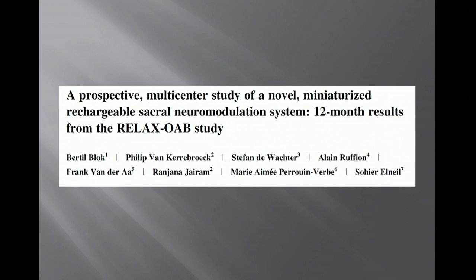This was developed because the current sacral neuromodulation has a non-rechargeable battery requiring exchange on average every 4.4 years. This new device with a rechargeable battery has a calculated lifespan of up to 15 years, meaning patients potentially would not need revisions for 15 years, with estimated cost savings of $12 billion over that period.